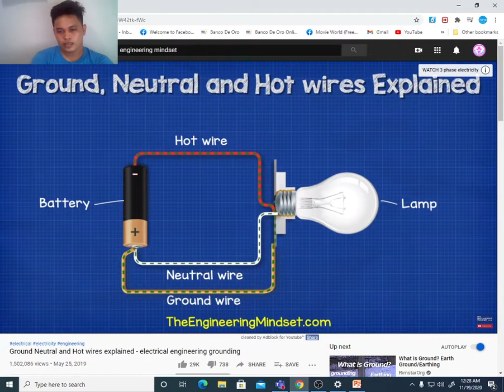If the hot wire is connected to both the neutral and the ground, then it will flow through both wires back to the source. But as the ground wire has less resistance, more current will flow through it.